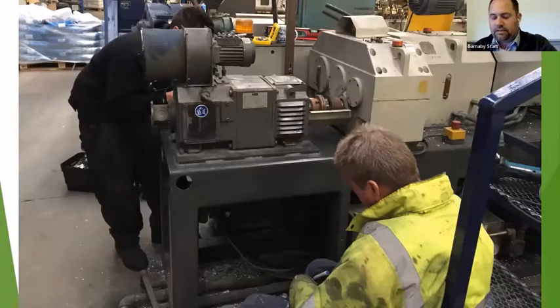So the torque developed by this new AC motor exceeded the old DC, but it wasn't quite as quick on the RPM, being a four pole. We didn't have to worry about torque because we could develop the torque with the encoder all the way down to zero speed. So we could produce 100% torque, and the inverter actually had an overload of about 150% as well. So we could drive it another 50% above that to get the torque if we needed. In this particular application, we didn't need it. It just broke away fine with LV polythene again on the extruder.